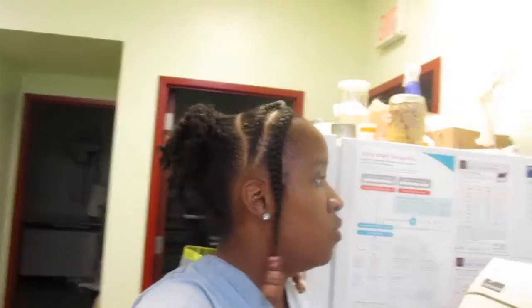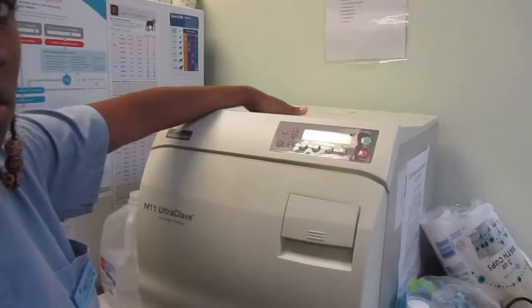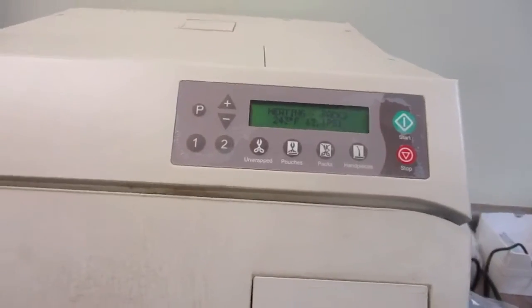So some autoclave maintenance, we have a daily, weekly, and monthly checklist. So daily, we want to clean the external surfaces of the autoclave and wipe everything down and disinfect it. And we want to inspect the gasket inside to make sure there's no tears, no rips or damages to that. And then we also want to make sure that when we do sterilize that no steam is venting from the autoclave machine. So now it's actually sterilizing right now, but we don't see any of that.